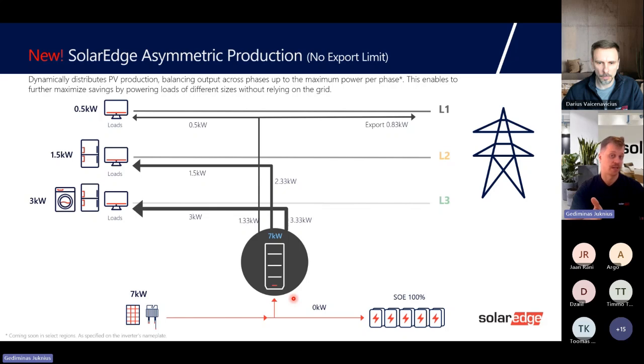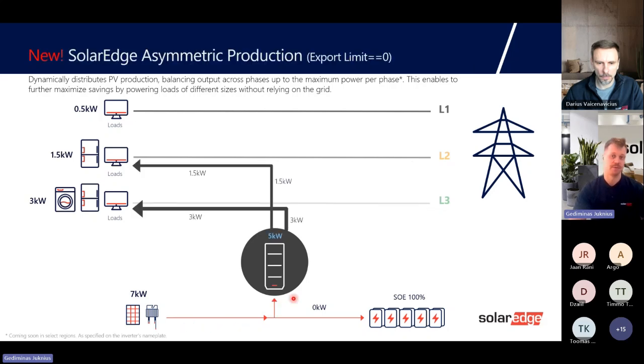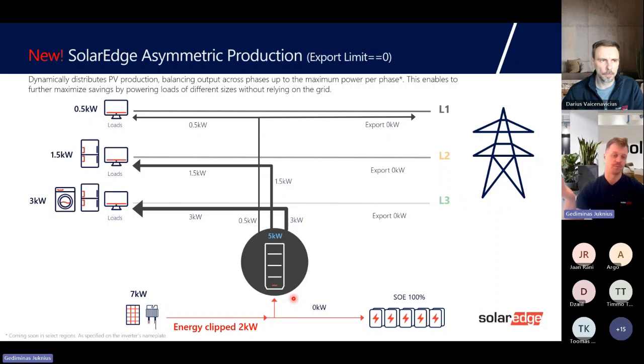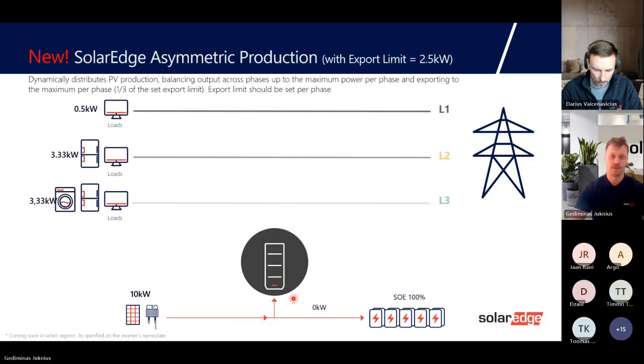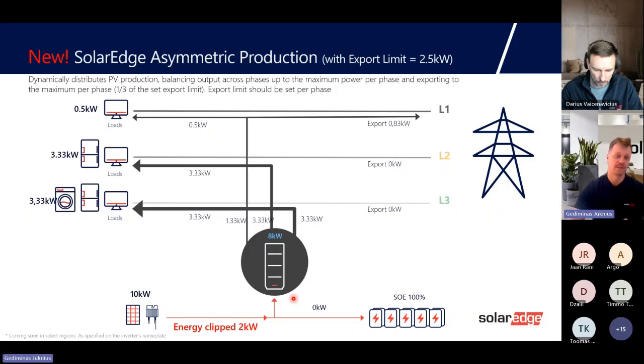One scenario is that there is no export limitation. So the inverter adapts production per phase to the loads in the house, and the rest is exported. Simple. If the customer has a zero export limitation, the inverter, first of all, adapts to the load and charges the battery. If consumption is lower than the production, the inverter will do clipping and zero export and supply as much energy as it needs per phase. If you have, let's say, a specific export of 2.5 kilowatts, again the inverter produces and charges the battery. Then if it's too much, it clips the energy and then exports what is allowed per phase. So on the SolarEdge inverter, the asymmetry works in all three scenarios we tested.